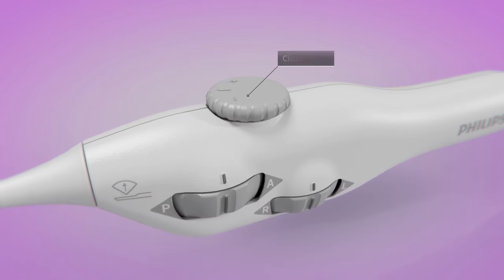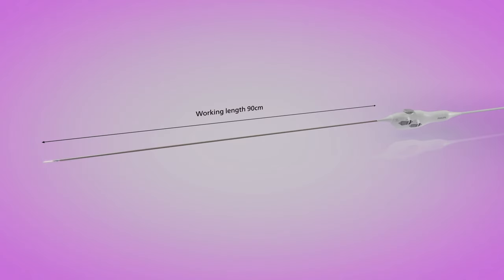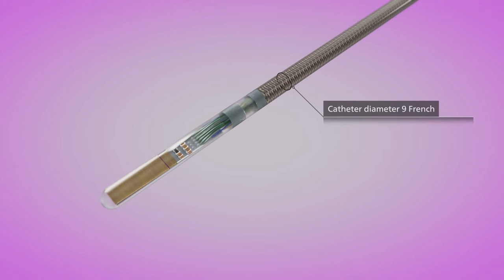The clutch knob provides variable tension to the flex wheels or can be fully engaged as a steering lock. The 90 cm working length supports access from the right or left groin and the 9 French catheter size requires only a 10 French sheath.